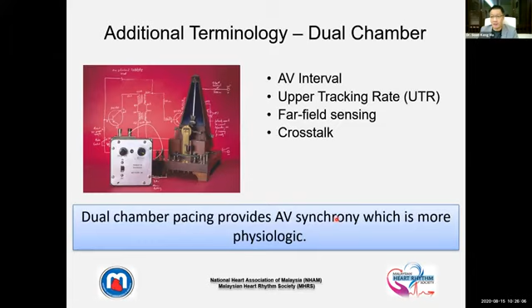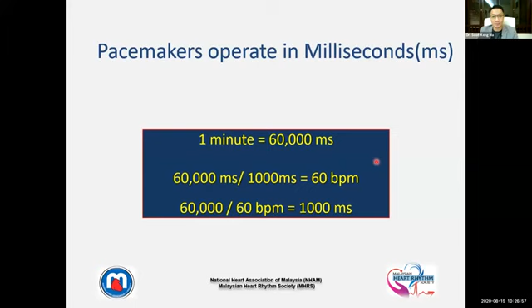Now, analogous to a clock that operates in ticks, a pacemaker also ticks, but the ticks are in milliseconds, very fast. As a pacemaker fundamental learner, we need to understand this formula: 1 minute equals 60,000 milliseconds. So if you want to talk in the language of a pacemaker, you need to talk not in beats per minute, but in milliseconds. How to convert that? Easy. Take 60,000 and divide it by the number of beats per minute, and then you get the milliseconds that you want. Okay, timing cycles.